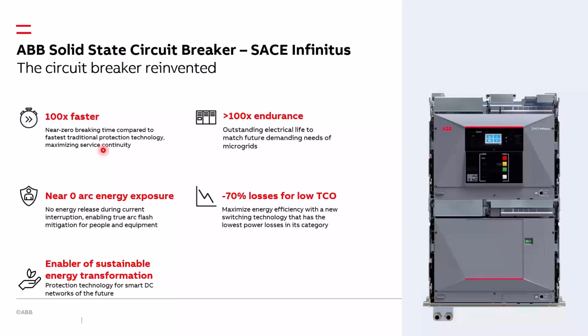Just to give you an idea, if we talk about an air or power circuit breaker, the interruption time is tens of milliseconds. Here we are talking about an interruption time of 100 microseconds. So, as I said, it is 100 times faster. Also, in terms of the capability to interrupt the current, we have 100 times the number of operations in load condition. Near zero arc energy exposure, because thanks to its very fast interruption time, we can limit the energy released during an arc flash event, so we can reduce the arc flash hazard.